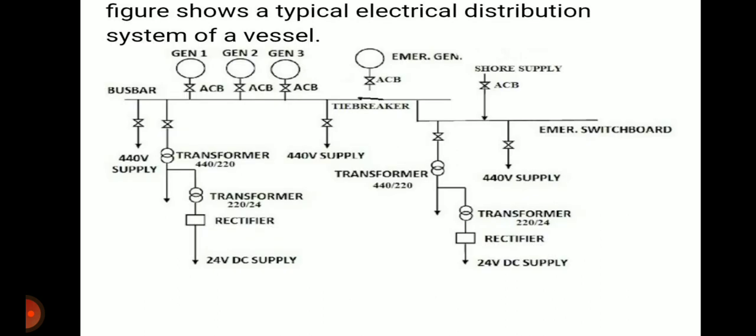In the typical diagram, three generators can be seen. Between each generator and the bus bar there is an ACB — air circuit breaker. From the bus bar, 440 volt supply goes out directly, then 220 volt via transformer, and 24 volt via transformer and rectifier for DC power supply. Shore supply lane and emergency generator lane with air circuit breakers are also visible.